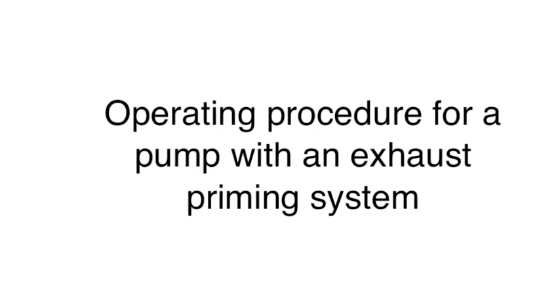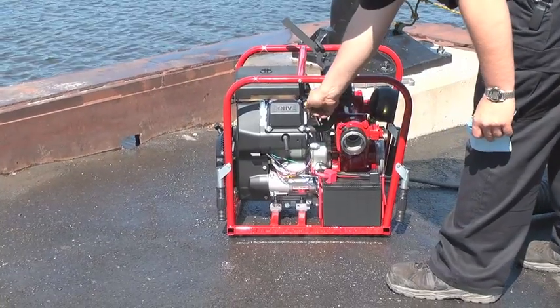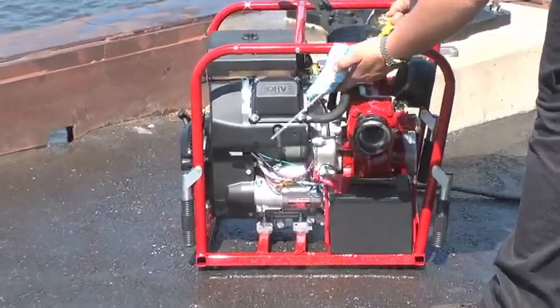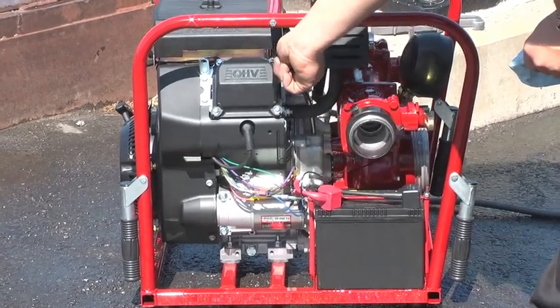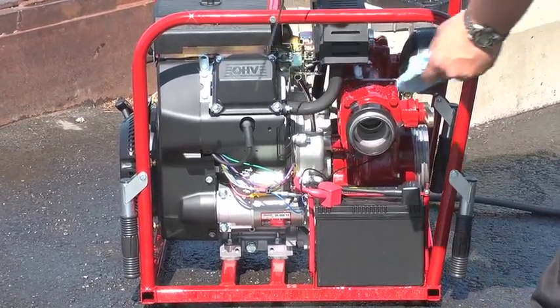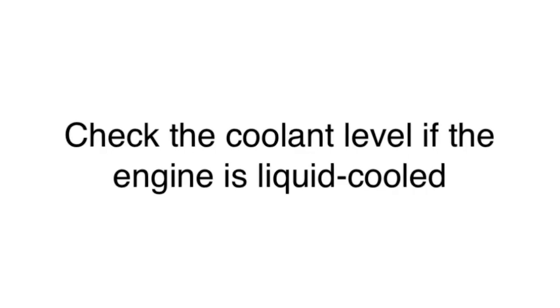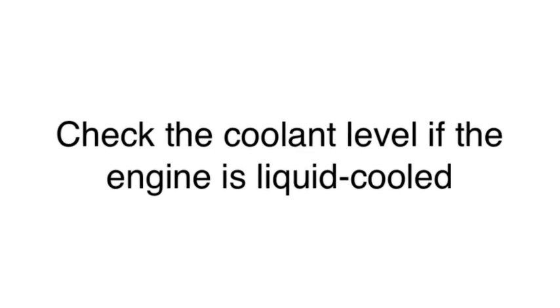This is the operating procedure for a pump with an exhaust priming system. Check the oil level of the engine. If the oil level is low, refer to the engine manual — it will tell you what oil is to be used. Check the coolant level if the engine is liquid cooled. If the coolant level appears low, check the manual.